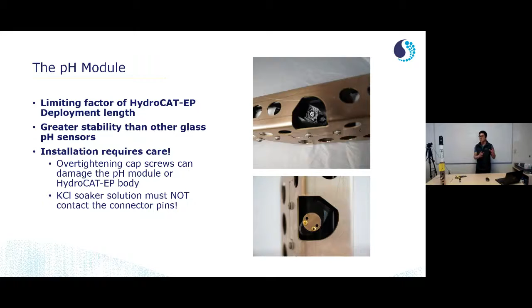Comparing this to the pH module on the HydroCAT EP V1, if we put them next to each other, they look pretty similar. Visually, this plate on the top is really the only major difference. That being said, the previous pH module and the previous HydroCAT EP screwed in with only 1 screw. There's only 1 screw that connects this pH sensor into this spot on the HydroCAT EP V1. Whereas now we have 2 screws for extra security. That's to ensure that you get a really strong connection, get a good seal on that connector, and your pH sensor is going to last for the entire deployment. So keep that in mind. That's one of the primary differences between the HydroCAT EP V1 and the V2.